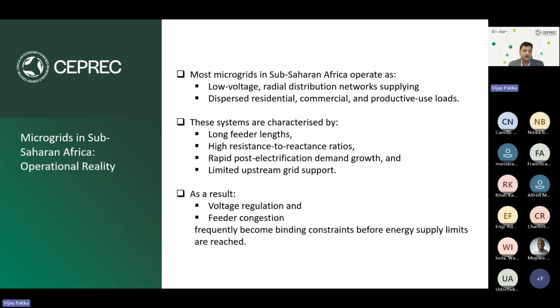Coming back to the operational reality of microgrids within this region, they're mostly made up of low voltage, mostly radial distribution lines, that is one single path of electrical power supply to the consumer, with dispersed residential, commercial, and productive use loads, and less of big scale industrial loads. These systems are mainly characterized by long feeders, high resistance to reactance ratios, and limited upstream grid support.